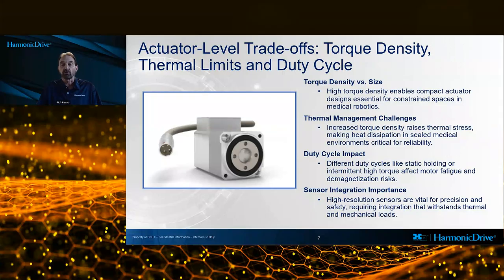Actuator-level trade-offs: torque density, thermal limits, and duty cycle. At the actuator level, medical system designers must balance competing requirements related to torque density, thermal performance, and operating duty cycle. High torque density is often required to achieve compact joint designs, particularly in robotic arms and imaging gantries, where space is highly constrained. However, increasing torque density typically increases thermal stress on the motor and surrounding components. In sealed medical environments, heat dissipation is limited, making thermal management a critical reliability concern.